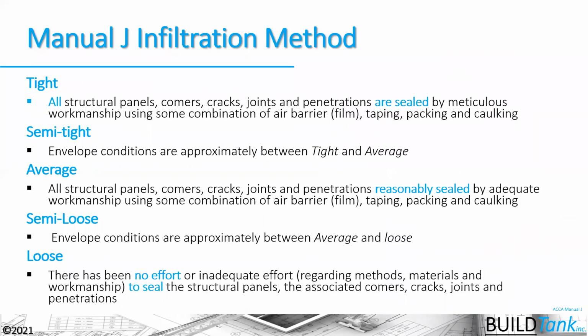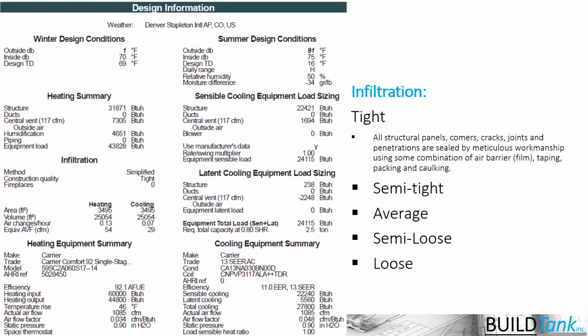So the estimated infiltration method in Manual J is asking you to choose: is that house tight, semi-tight, average, semi-loose, or loose? And this is the description of what that ultimately means. You can look at the actual design information and determine what they chose here. In this case, they chose tight, which says that a structural panel has been used, and that the corners, cracks, joints, and penetrations are sealed by meticulous workmanship. So how do I know if meticulous workmanship has actually been used in the construction of that house, when I've designed this HVAC system way before the house was ever being built?